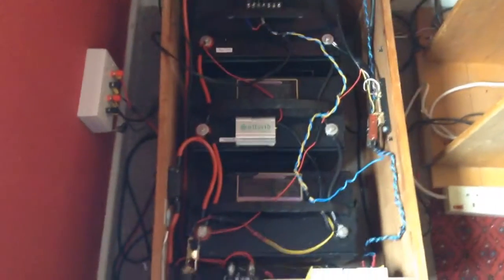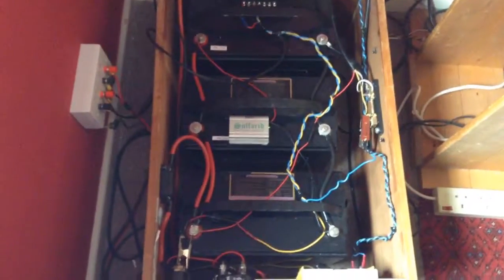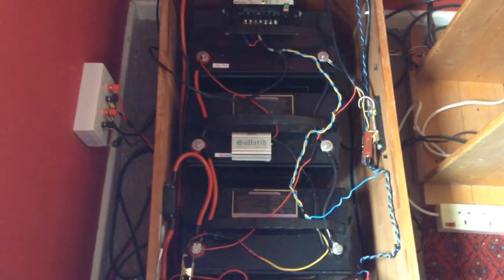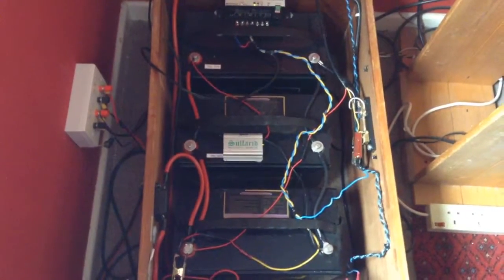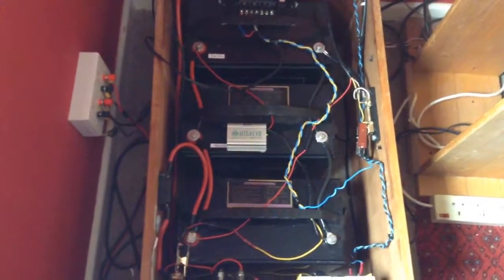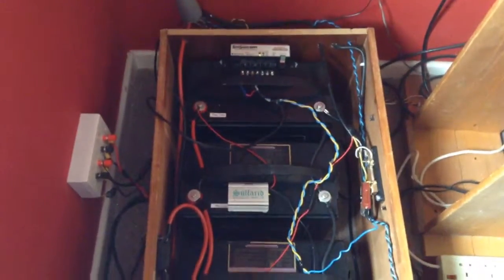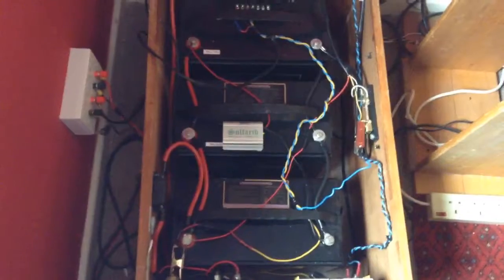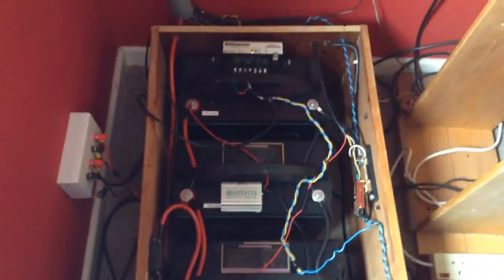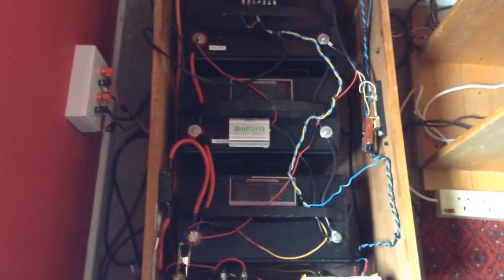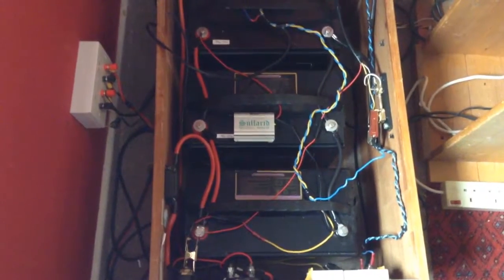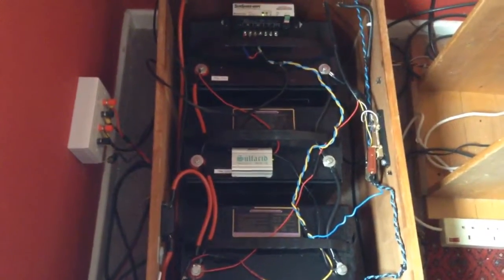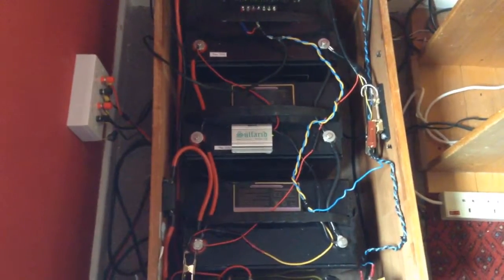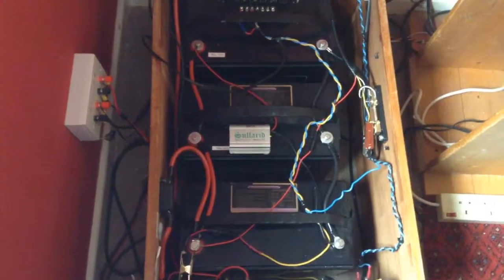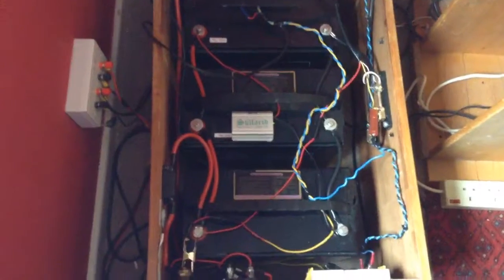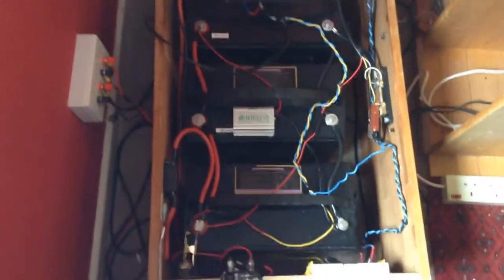So indoors, I would recommend that you use sealed lead acid batteries. These are sealed AGM batteries. The AGM stands for Absorbed Glass Mat. There is no free liquid inside the batteries, so if they got broken for any reason, the casing cracks for example, nothing would leak out, so no harmful acid would leak out. Also, since these are sealed batteries, they don't vent off any hydrogen gas under normal conditions. They have small valves inside that, if you seriously overcharge them, would vent off, but under normal conditions, they recombine the gases produced inside the battery. So they are 100% safe to use indoors.